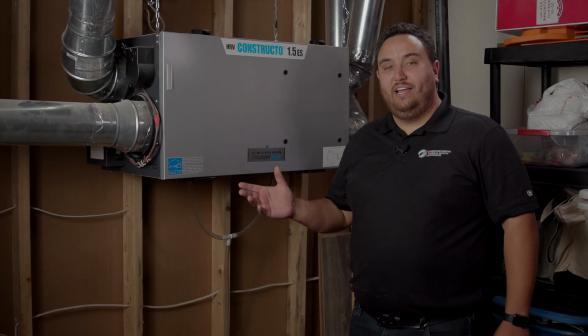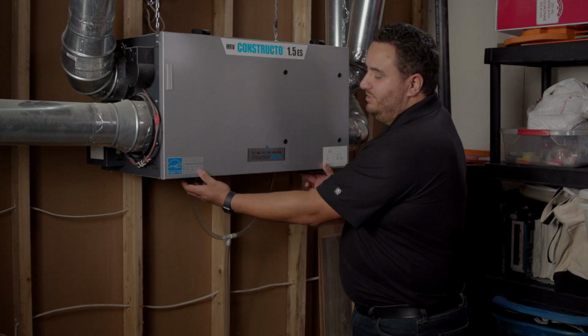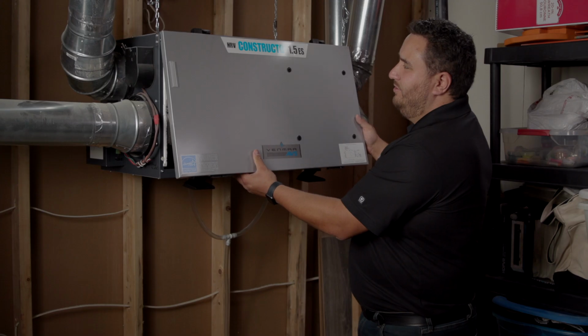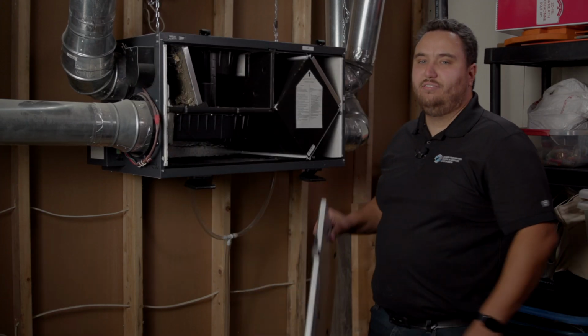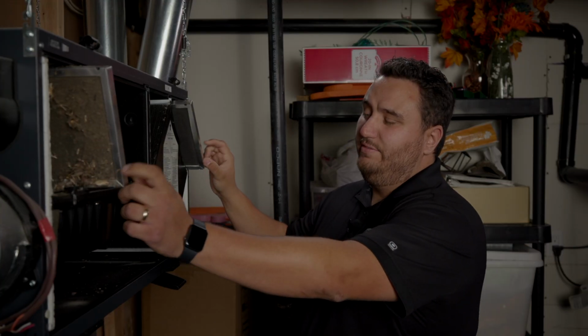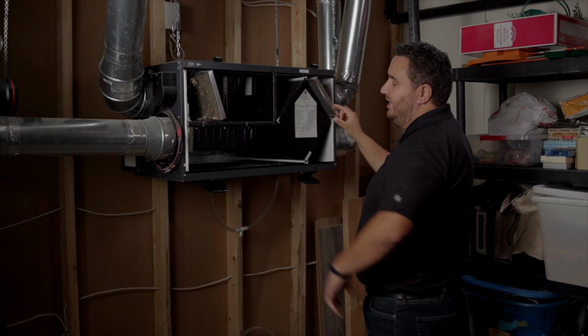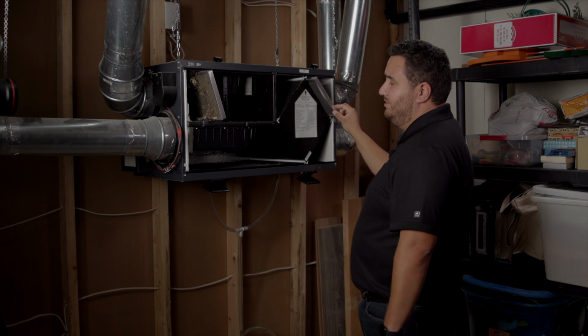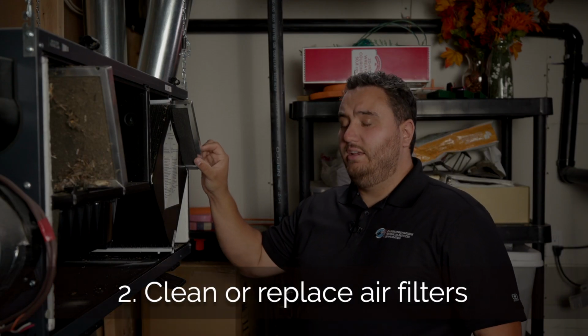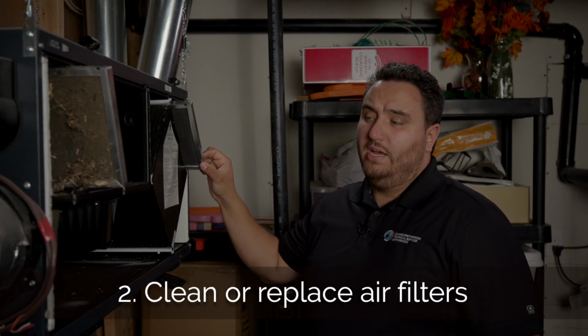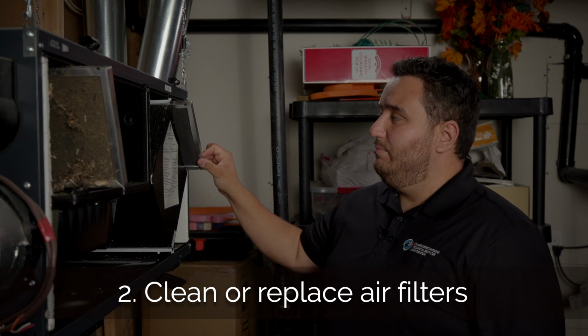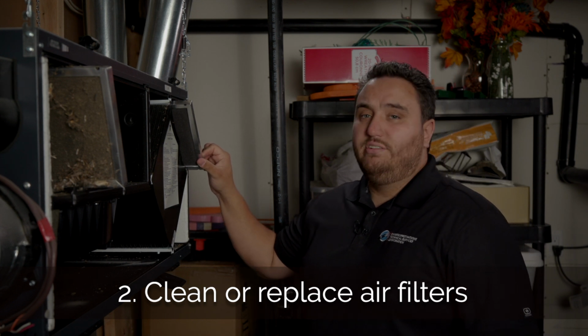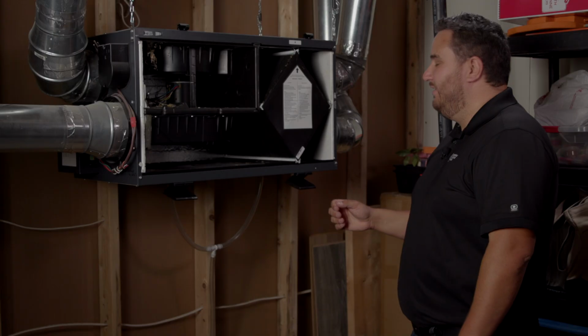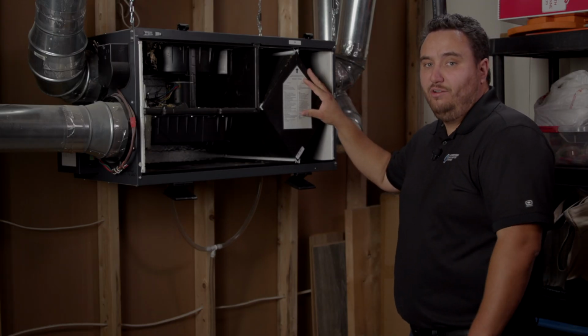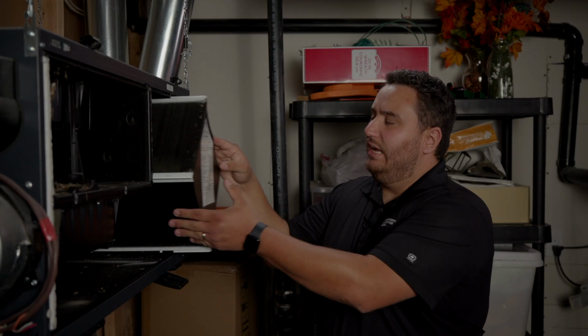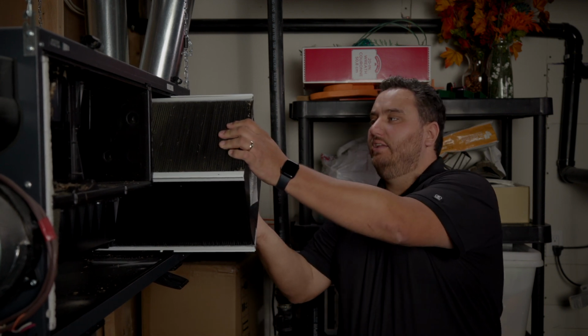Let's go ahead and open up the HRV. Most units will have 2 clips on the bottom, and the door will actually slide off. Most HRVs will have 2 filters that can be removed. They can be washed in warm water with mild detergent. Older units may have filters that need to be replaced. Check your owner's manual for the size and type of filters, and contact your housing department for any assistance. Next, we're going to remove the heat recovery core from inside the HRV. Give it a pull, it might be stuck, so be careful with it.